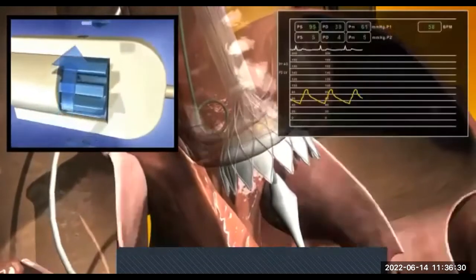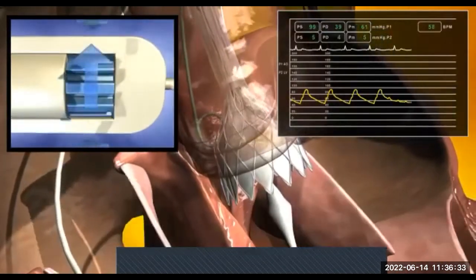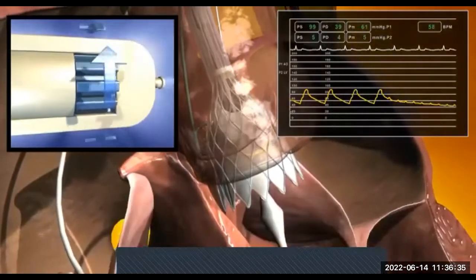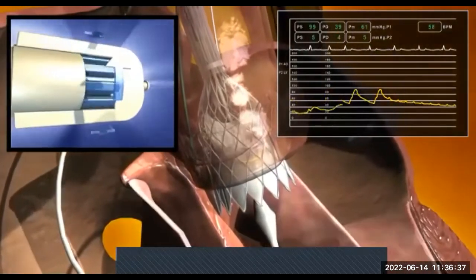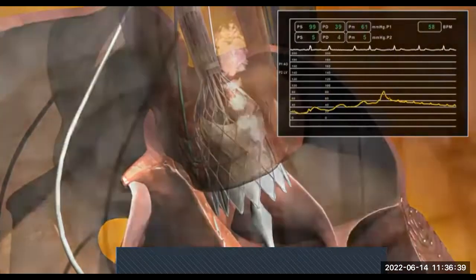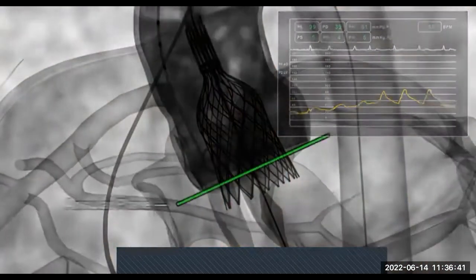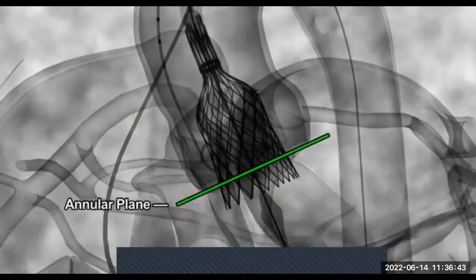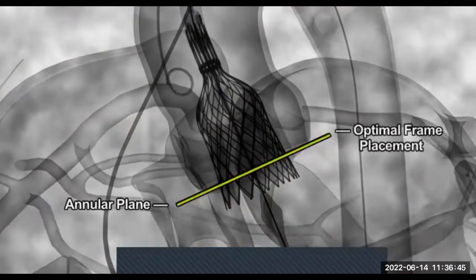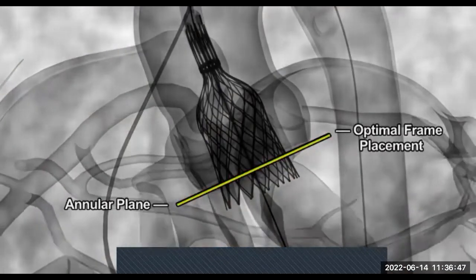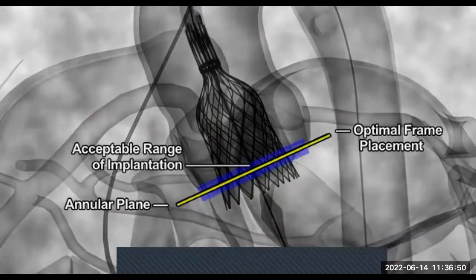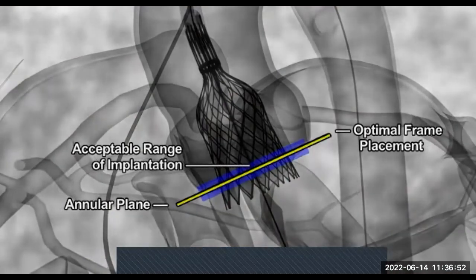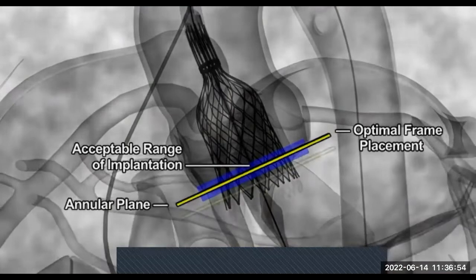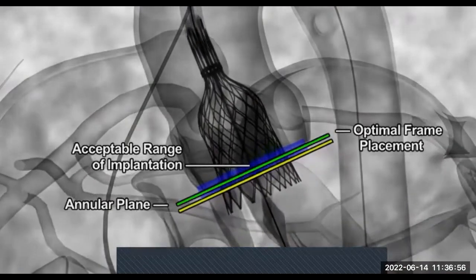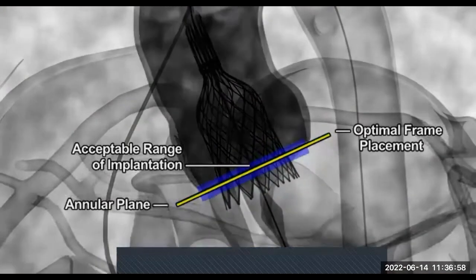Note, during this stage, the blood pressure will drop. It is important not to stop deploying until blood pressure rises to normal parameters. Stop deployment and perform an angiogram. Target placement is represented by the highlighted line being lined up with the bottom of the aortic root. The shaded areas represent an acceptable implantation zone for the valve. If the valve is positioned low, carefully pull the catheter to reposition the valve.